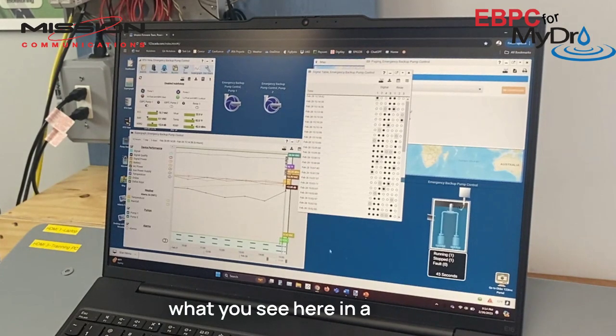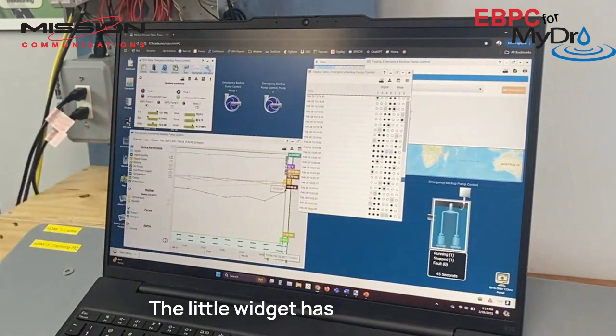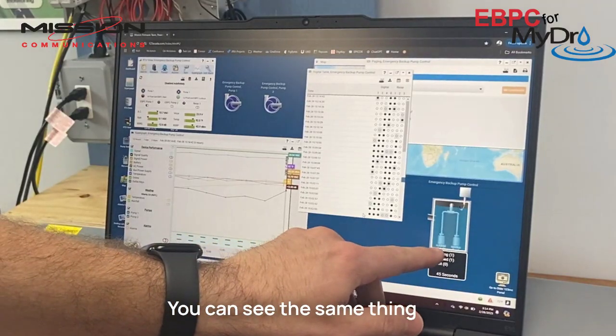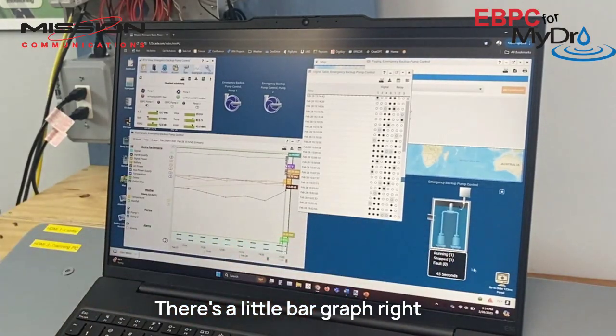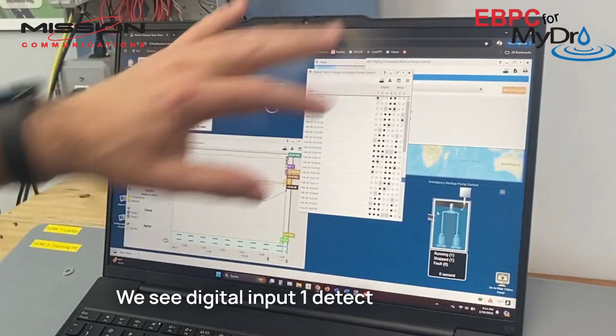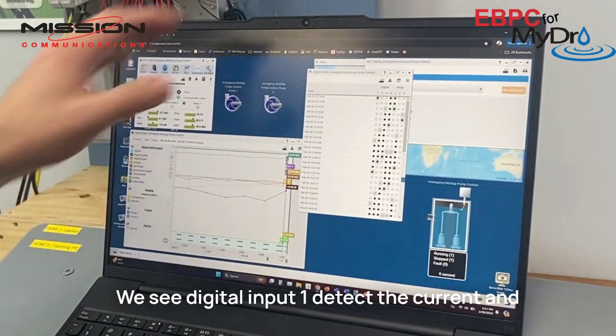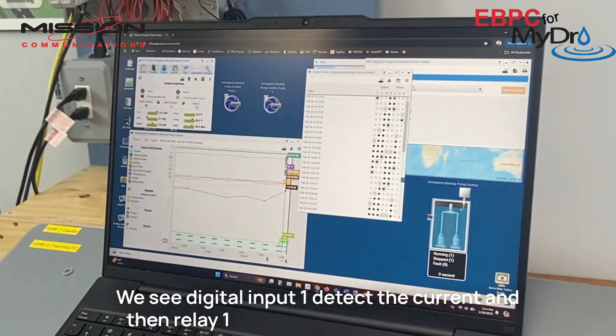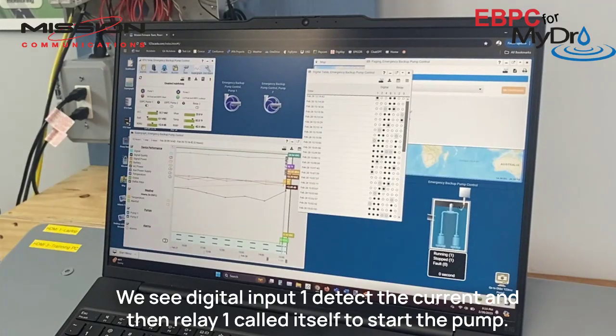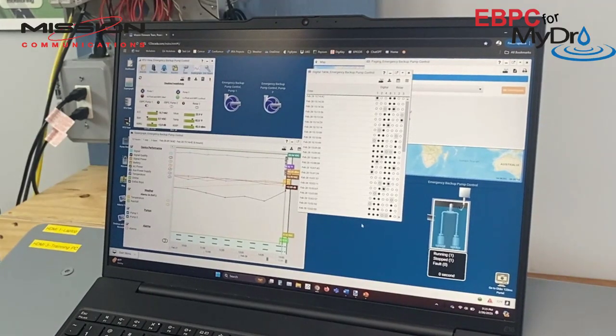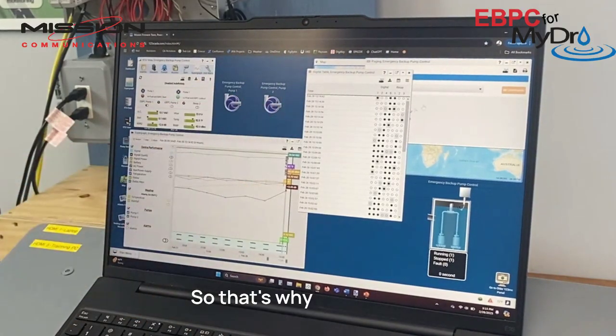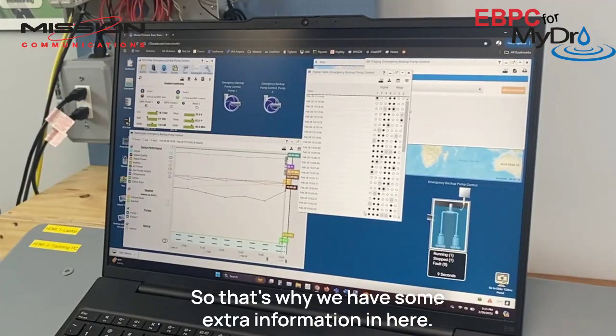What you see here in a second is the little widget has started running. You can see the same thing here. This little bar graph right there start moving. We see digital input 1 detect the current. And then relay 1 closed itself to start the pump. I tipped it a couple times, so that's why we have some extra information in here.